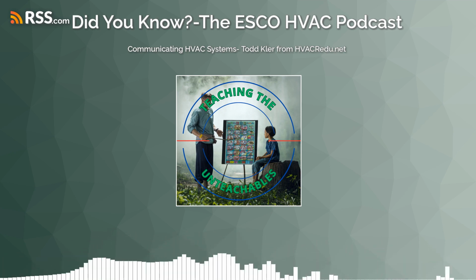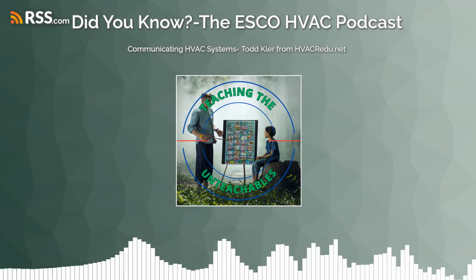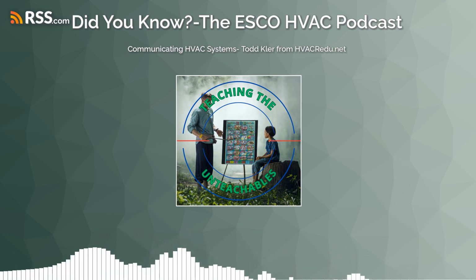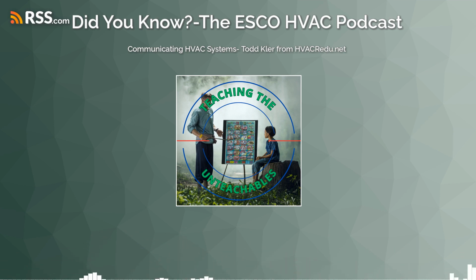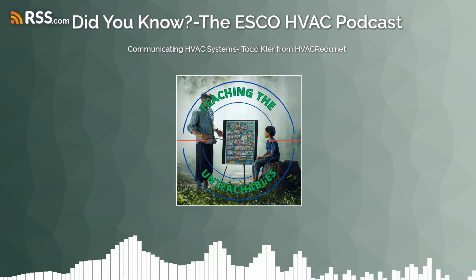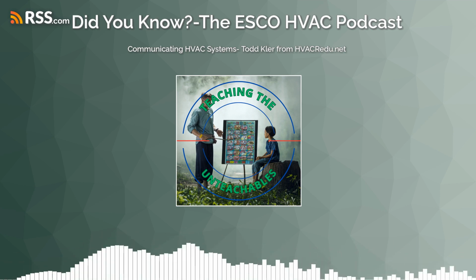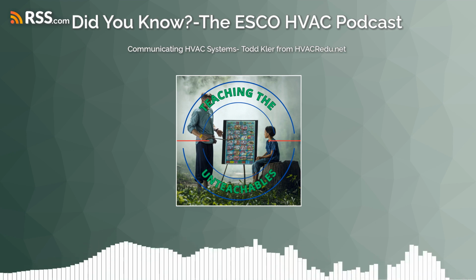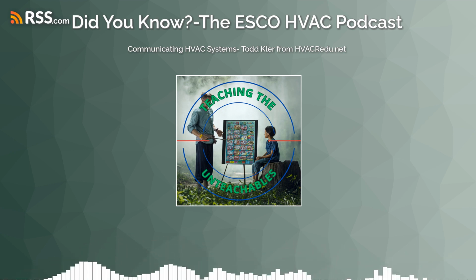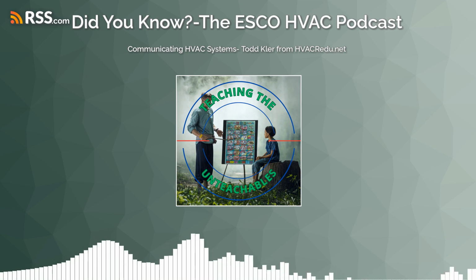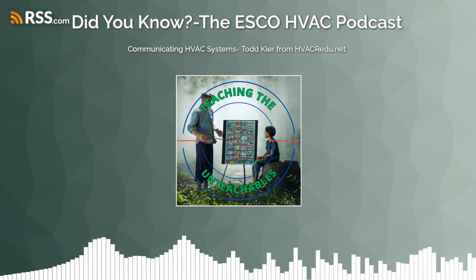That ground rod is absolutely important. And we got places out west that don't have ground rods. They have ground arrays where they have shallow, wide grounding. But it is absolutely in a dry condition, and it becomes less of a conductor. So it's very important to understand that ground is part of our communicating network. We didn't think about that before, but it is now.